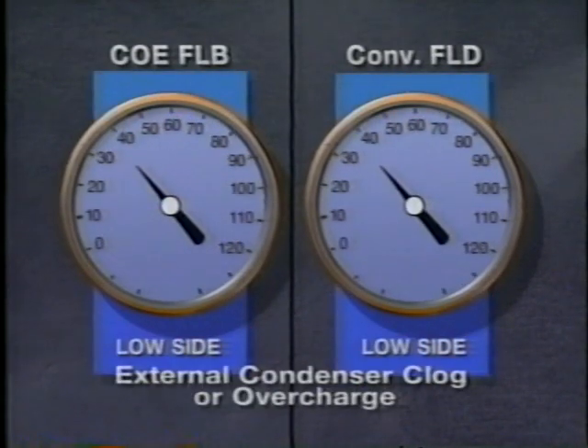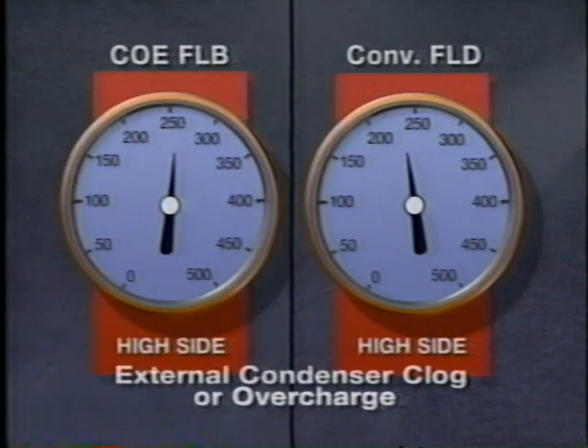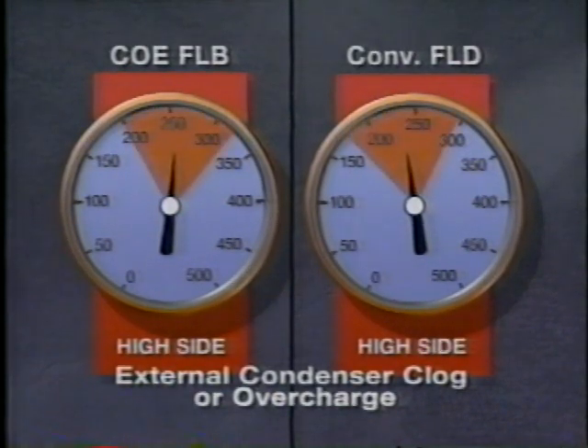If the condenser or radiator air passages are clogged, or if the system has been overcharged with refrigerant, both suction and discharge pressures will be high. If the air passages are clogged, the condenser and radiator fins must be cleaned. If the system is overcharged, refrigerant must be recovered and the system must be recharged with the correct charge.